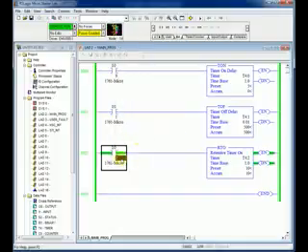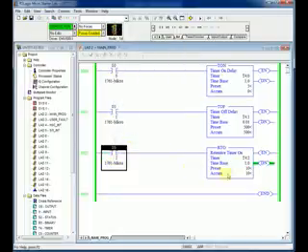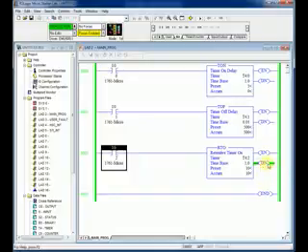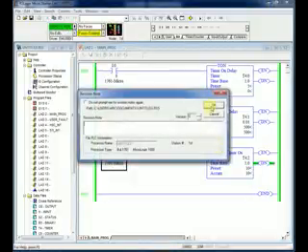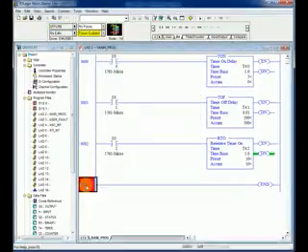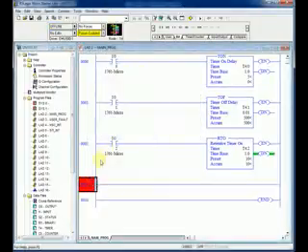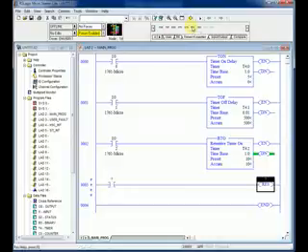Let's do that. Let's go to offline mode. Now let me take one rung and one input bit. Into the timer, you can see one reset. Let's take I:0/3. This is the input bit address. And the reset - what I want to reset, timer T4:2.